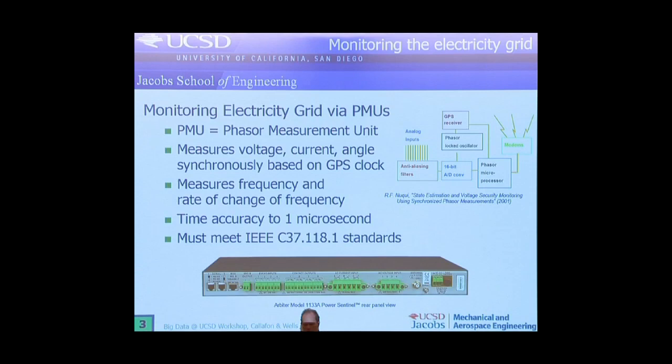So it means you can have these things distributed all over your electricity grid and they monitor the data at a synchronized rate, which is very important when things go wrong. There's a particular time accuracy up to about a microsecond, and there are IEEE standards used to qualify and guarantee these things are working properly.